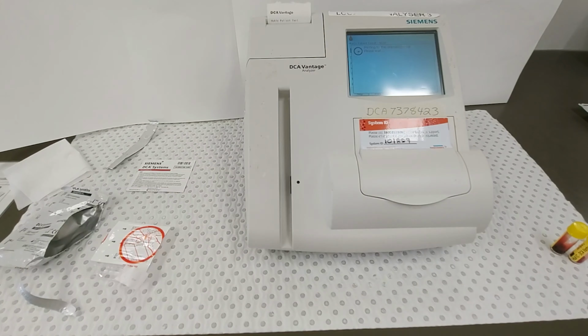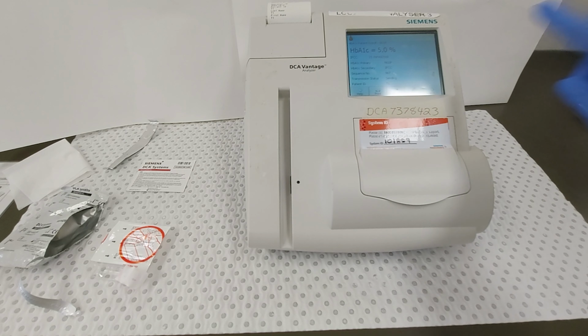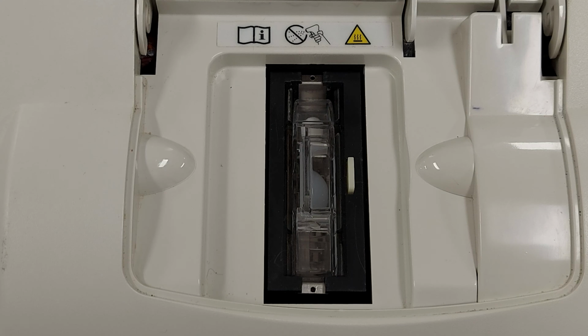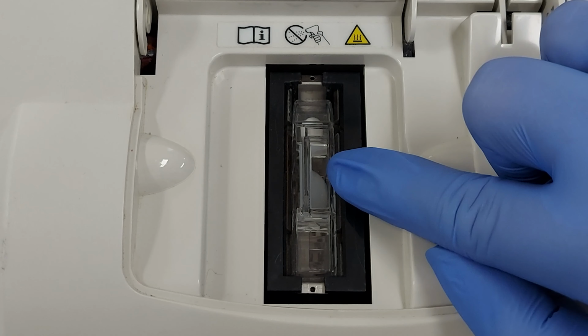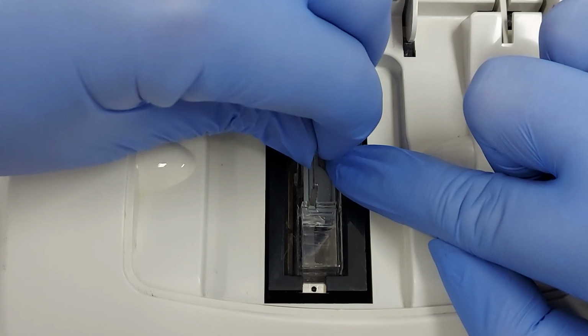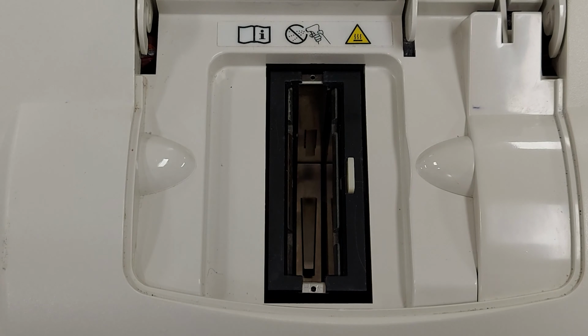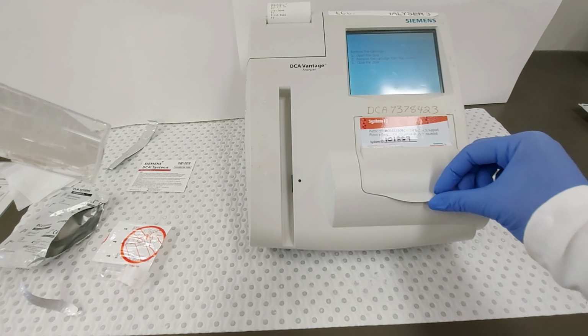If you require a printed copy of the results, hit the print key. Hit the send key to digitally export the result to the LIS. Once you have the results, hit the next key, and the display will prompt you to remove the reagent cartridge. Do this by pressing the white button on the right of the cartridge tab, and gently pushing the cartridge to the right while simultaneously pulling it out to disengage the clip. Close the door and you're done!